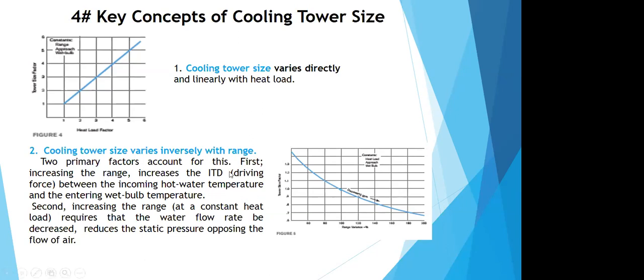And what is the theory? The reason behind this is that when you're increasing the range, the driving force, that is the enthalpy of the hot water and the entering wet bulb temperature enthalpy, increases. So this increase in the driving force actually reduces the tower size. The other important aspect of increasing the range is that you are reducing the water flow, and doing so, the static pressure drop of the fan reduces, which means that you can reduce the size of the fan, you can reduce the size of your motor, and you can reduce the size of your cooling tower as well.